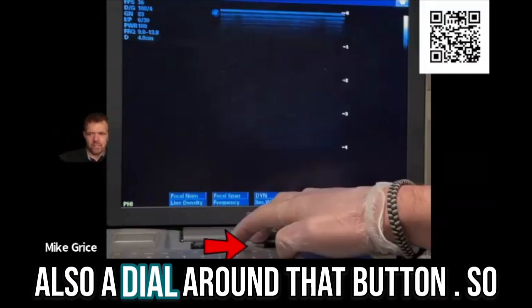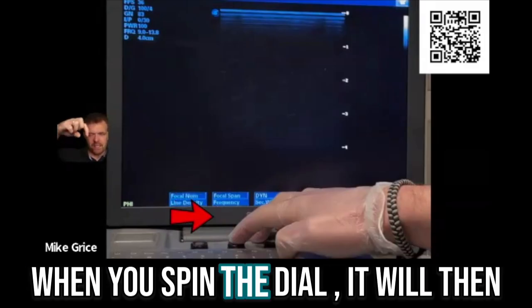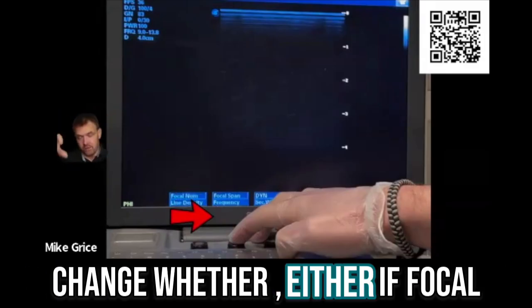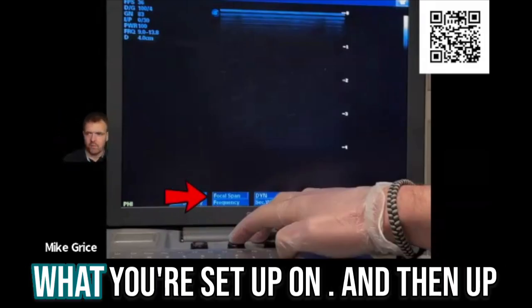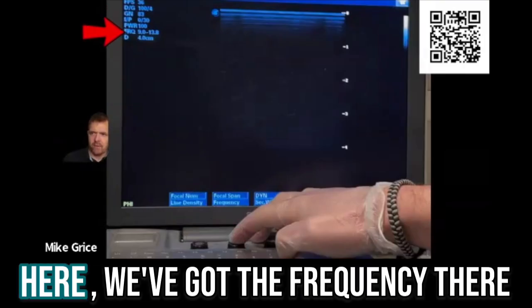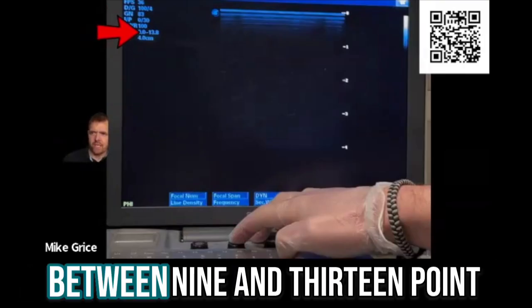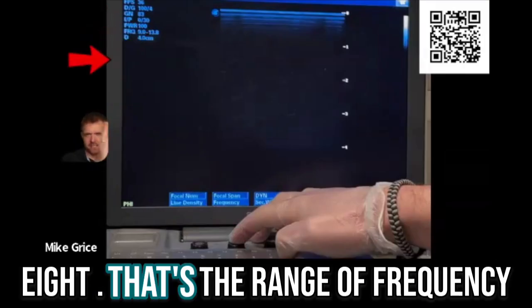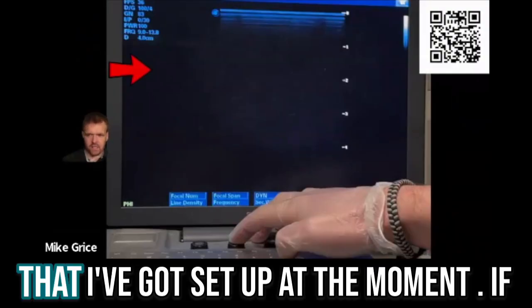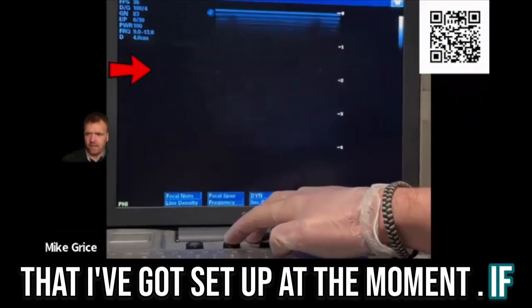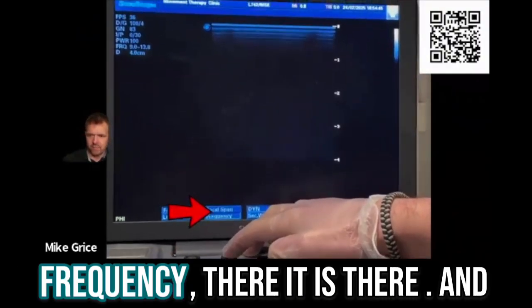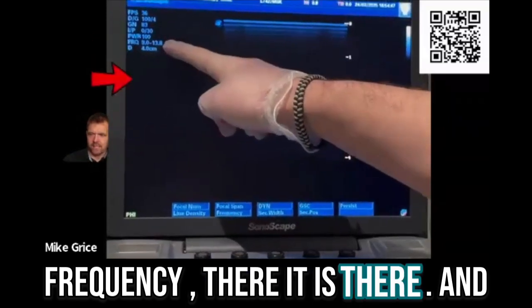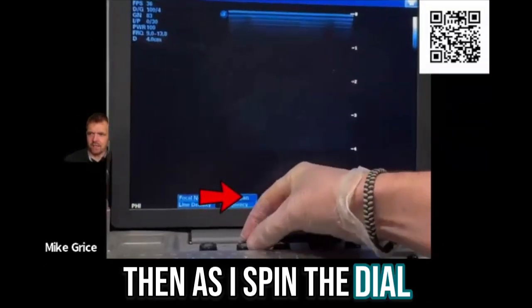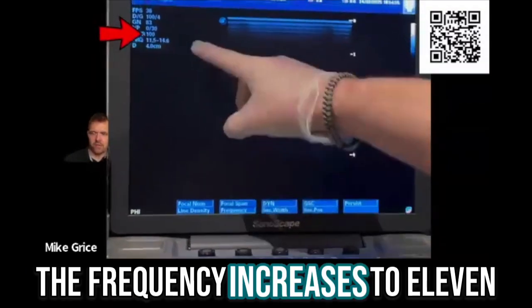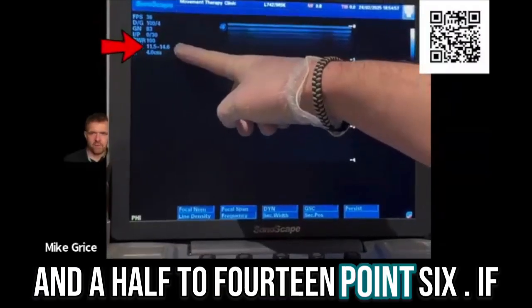And then there's also a dial around that button. So when you spin the dial, it will change either the focal span or the frequency, depending on what you set up on. And then up here, we've got the frequency between 9 and 13.8. That's the range of frequency that I've got set up at the moment. If I press that button, change it to frequency, there it is there. And then as I spin the dial, the frequency increases to 11.5 to 14.6.